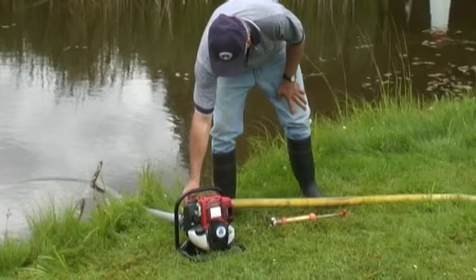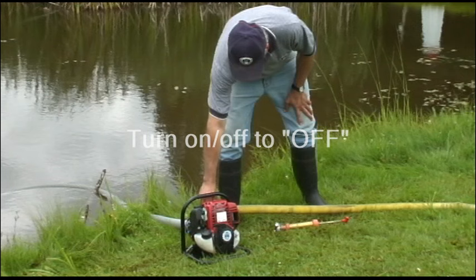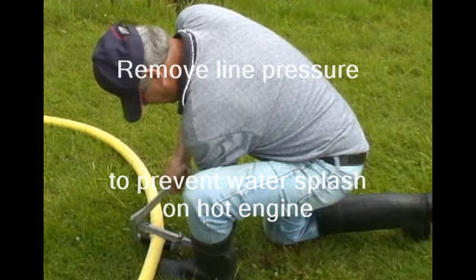When you are ready to shut down the pump, an idle period of at least a minute is important to allow the engine to cool down. After the engine has been allowed to cool down, turn the on-off switch to the off position. When disconnecting the discharge hose, it is important to prevent water from splashing on the hot engine. Therefore, it may be necessary to release the back pressure by either clamping the hose with a hose strangler or kinking the hose before disconnecting.